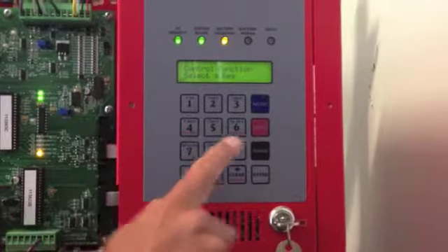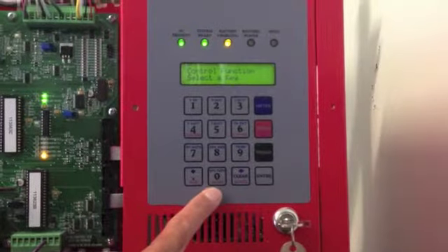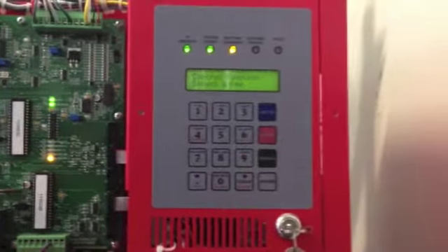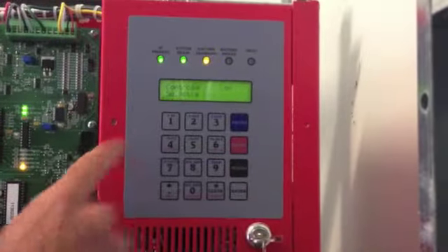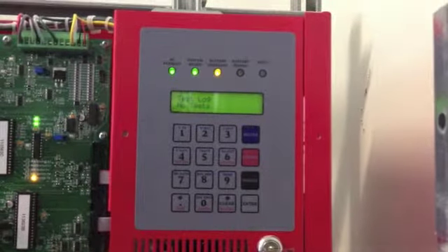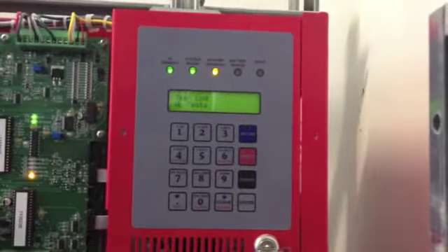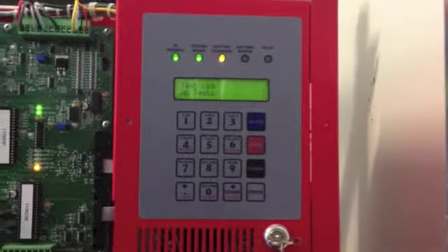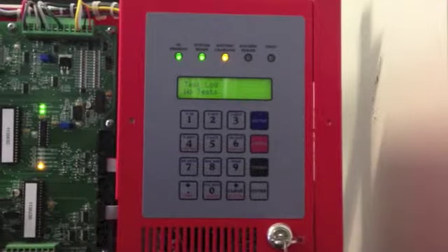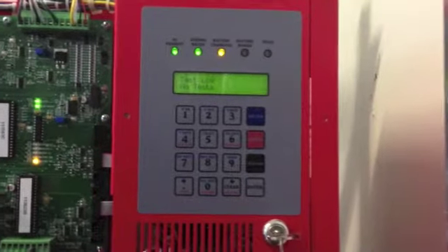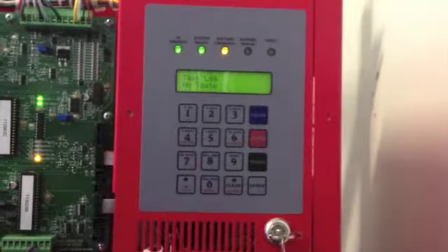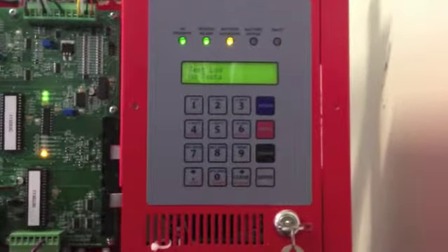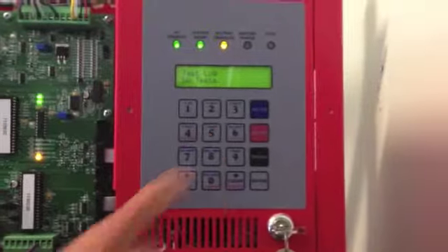We see test log, event log, and alarm log. Those are the 3 logs for the system. The test log, the system does a self-test once a month that's 5 minutes and an annual test that's 90 minutes. So we have 13 total self-tests a year. Everything is automatic, it's pre-scheduled for a given date and time, and then the duration is preset as well, 5 or 90 minutes. So all we have to do is come to our log and check and see did we pass our most recent self-test.